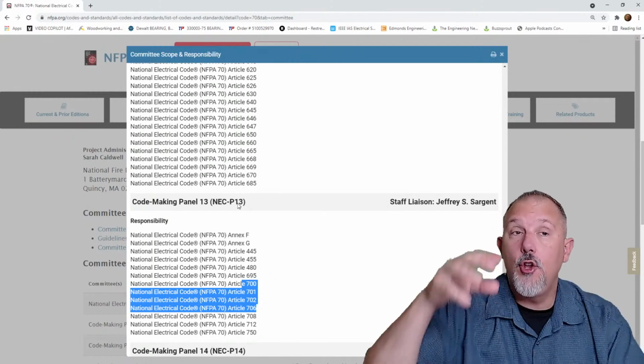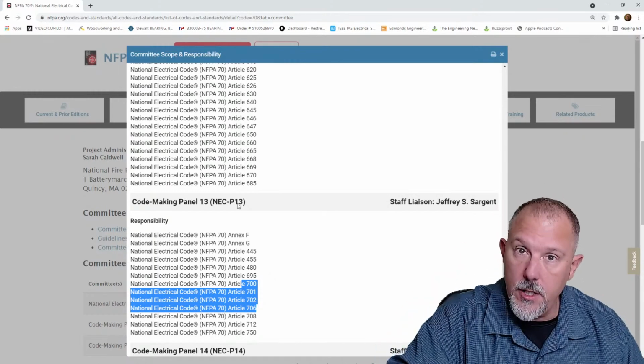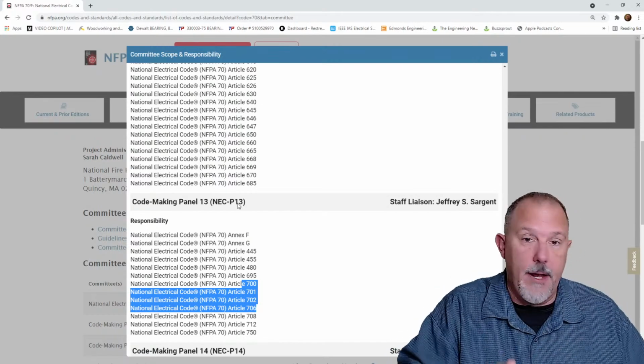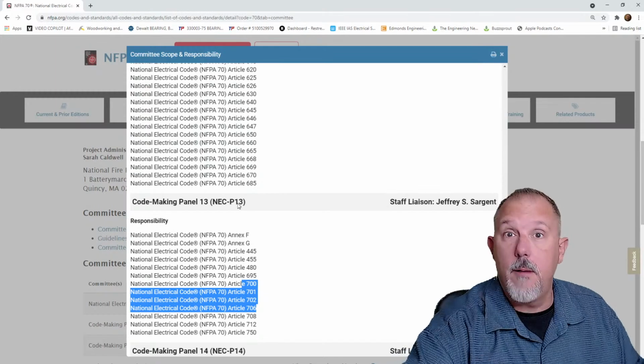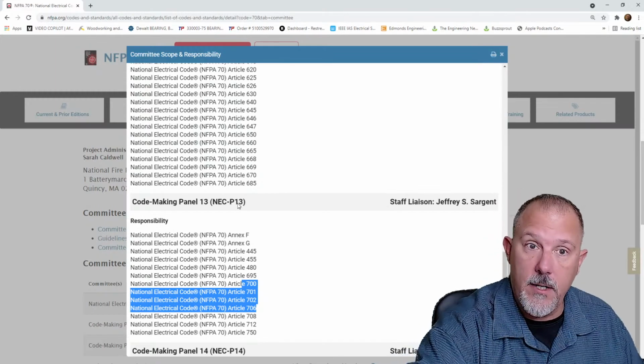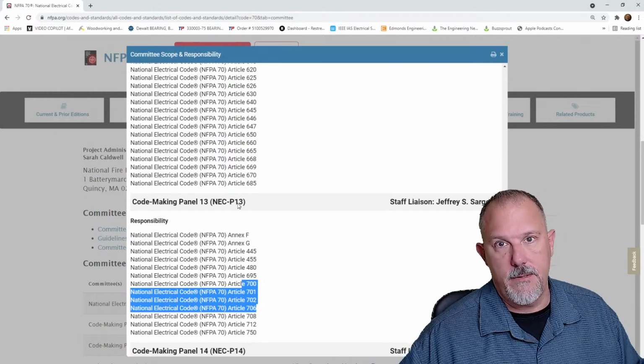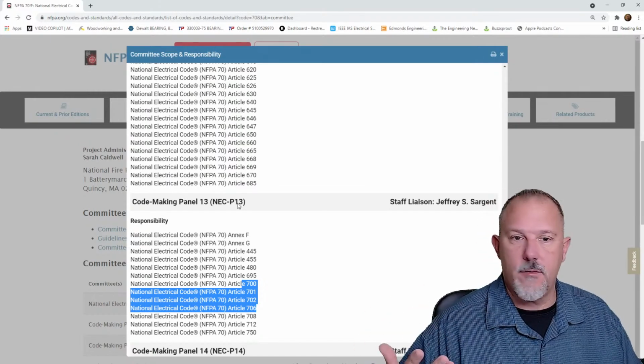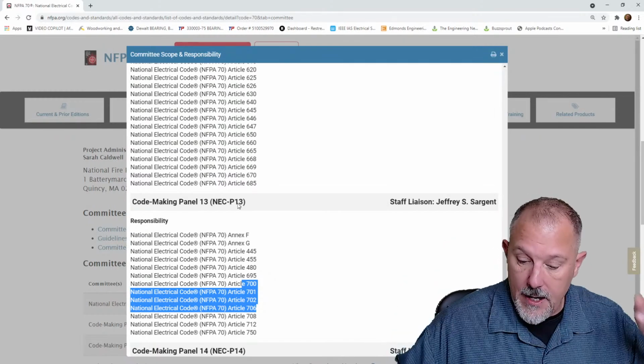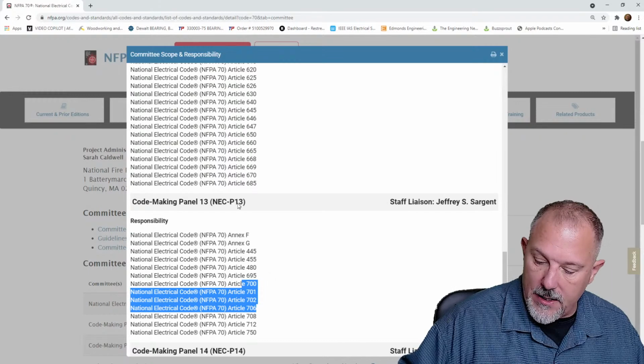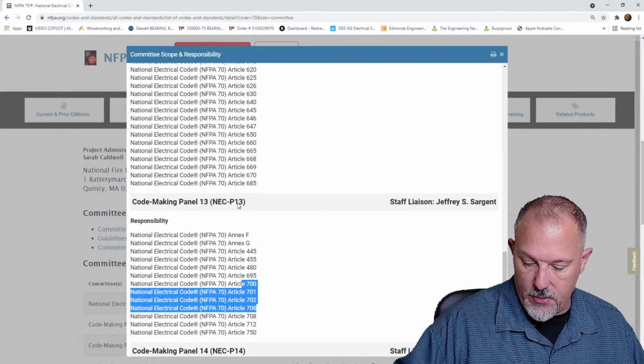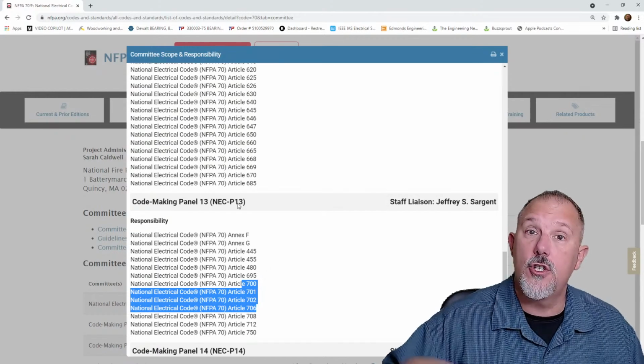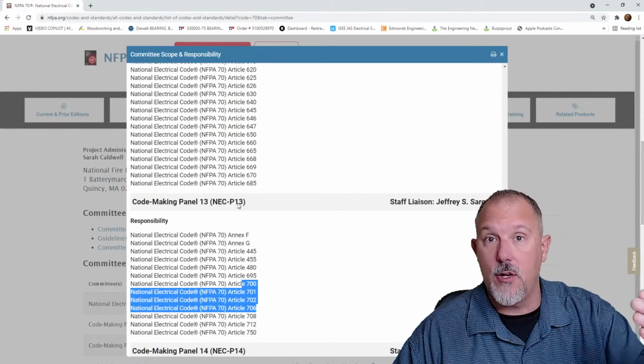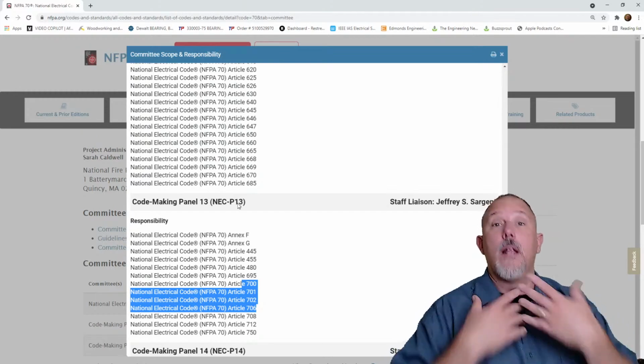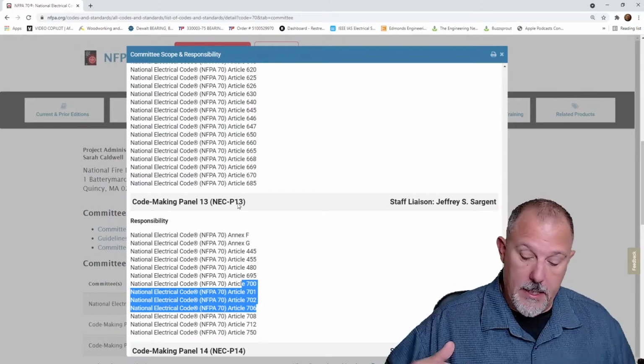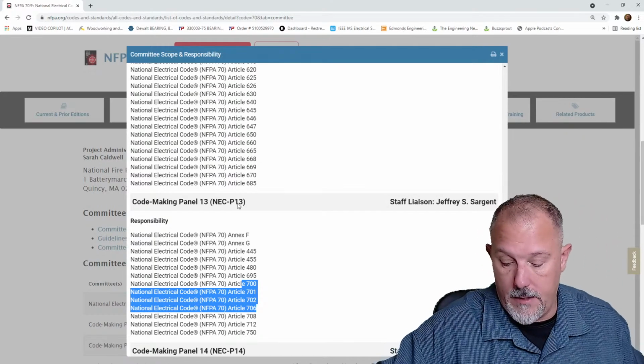This is why you might see a requirement in the code, like in this case, you have a selective coordination, and panel 12 said, hey, we want to mark the equipment that these are selectively coordinated. Panel 13 did not. So it's two different sets of eyes, two different reasoning. And I'll tell you why panel 13 didn't. They said that it's already in the language because it says the selection shall be documented and made available to those authorized to design, install, and inspect. So panel 13 did not feel the need to label the equipment. I personally like the concept of labeling the equipment, but they elected not to do that.